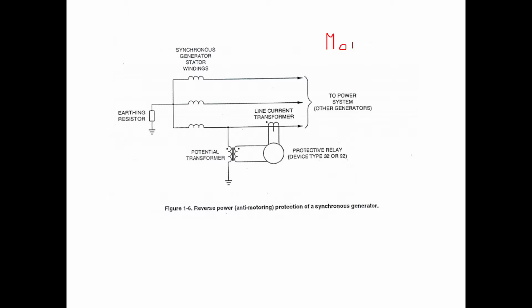When it is working as a motor, it is now a balanced load. So the current drawn by these three lines from the grid will be the same. So the reverse power protection is always a single phase protection. It's not a three-phase protection. Why is it a single phase protection? Because the current drawn by the motor is a balanced load.